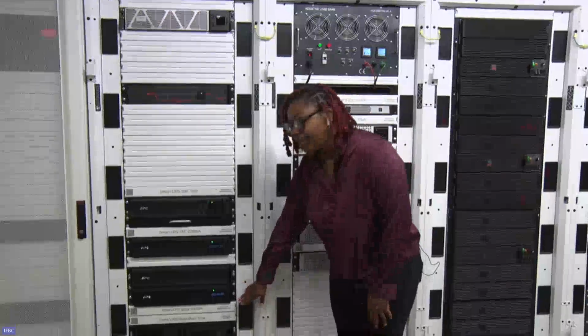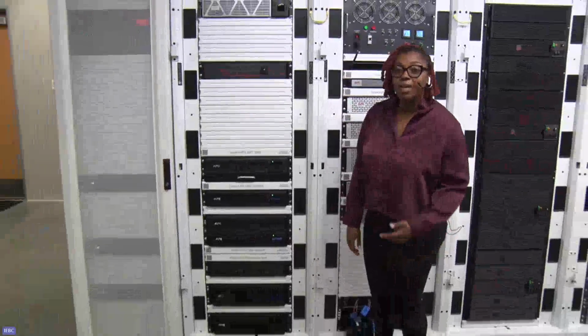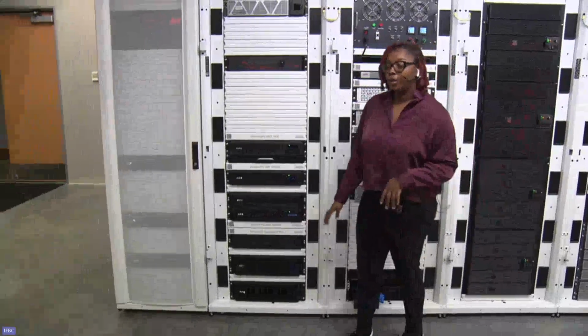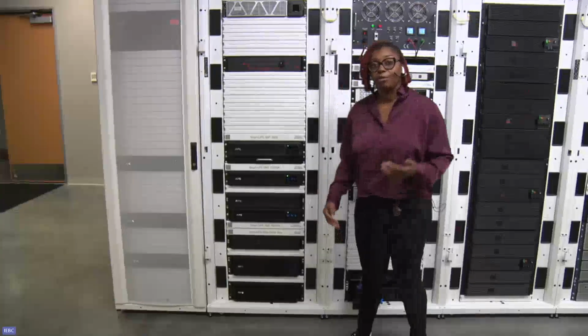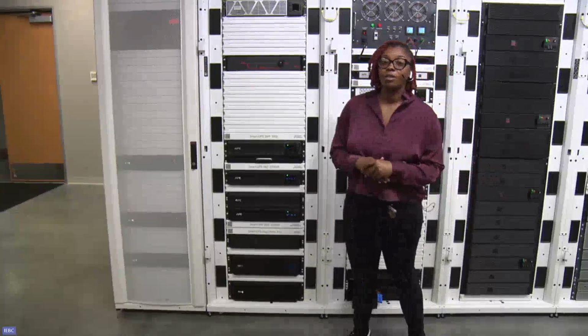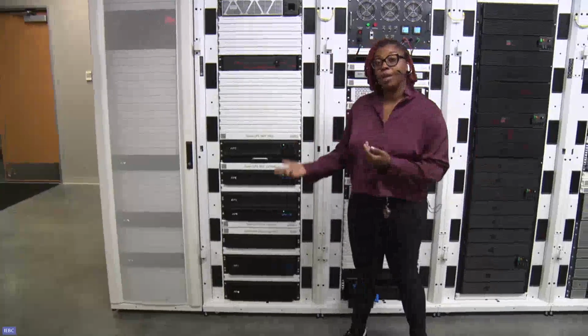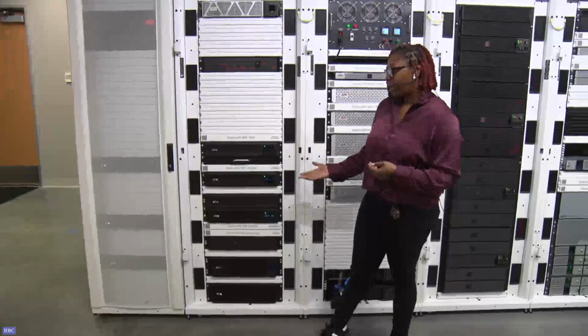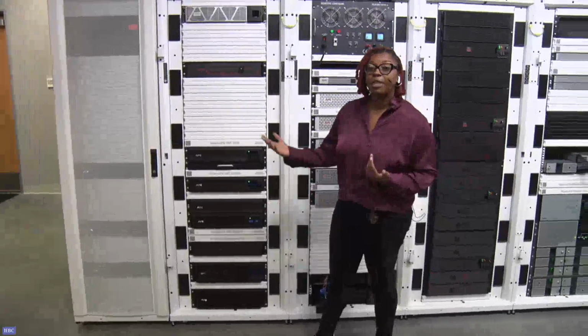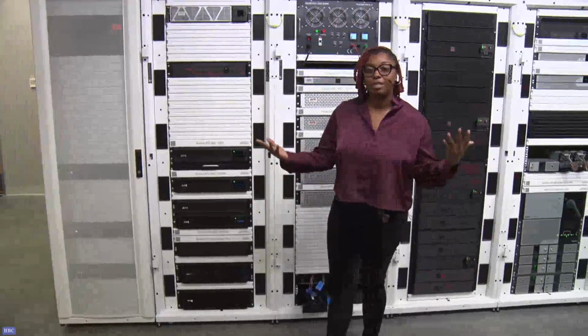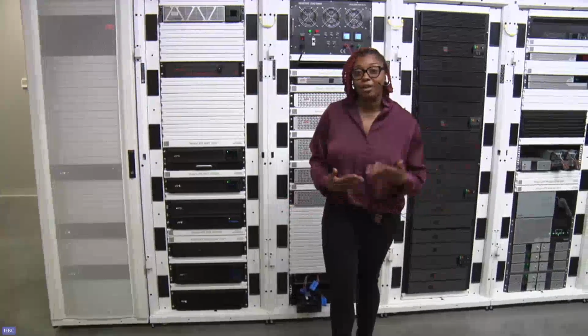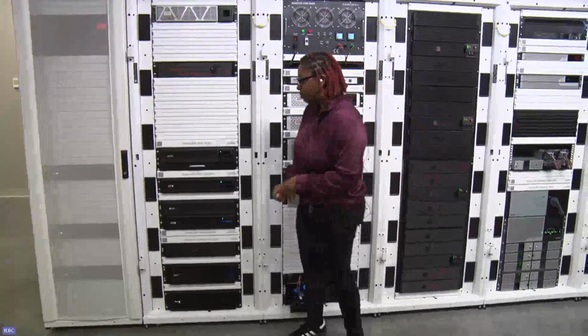Down here we have a SmartUPS SMX. When you hear X, think extended runtime—with this you can add external batteries. Runtime is really important; if there's a complete outage and you rely on battery, you may add additional batteries to get more time to safely save critical data or shut down the UPS system.